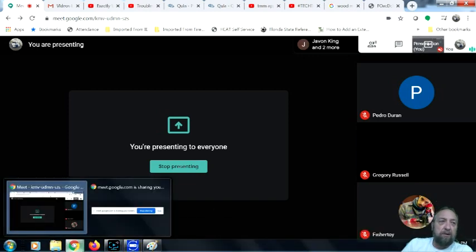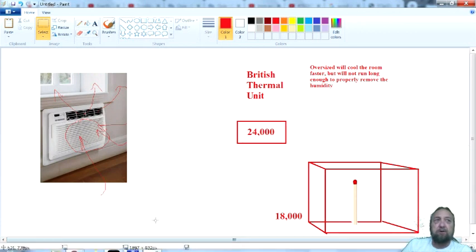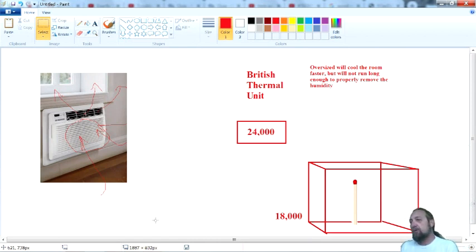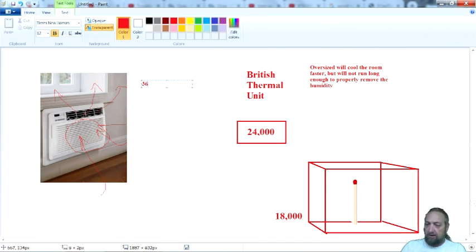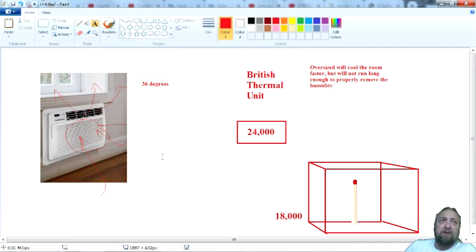So anyways, what I was saying with the air conditioner is that when you look at a refrigerator, if the customer says it's not cooling properly, you want to look at the evaporator and the frost pattern on the evaporator. If it's got a small white frost on the entire evaporator, it has the right amount of Freon inside of it. Well, air conditioners don't freeze up. They run their evaporators at approximately 36 degrees. Okay? So it's just above freezing on the evaporator.